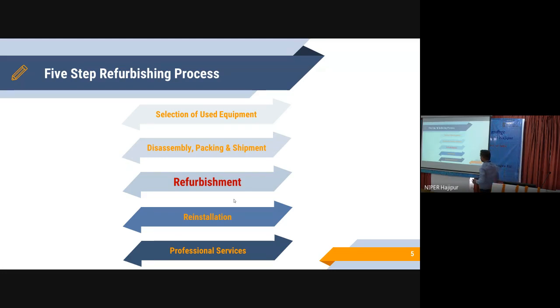The second step is the disassembly, packing, and shipment. The party who is performing the refurbishment, they have to make sure that during the disassembly, no part of the medical device or equipment gets damaged. They have to pack like that, and then they have to ship the old or used medical device to the facility where refurbishment has to be performed. Now the third step is the refurbishment.